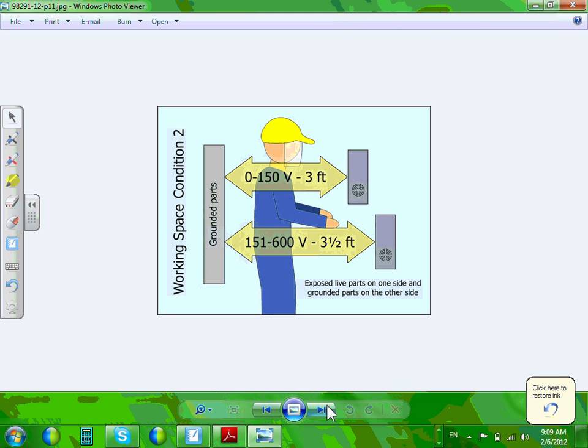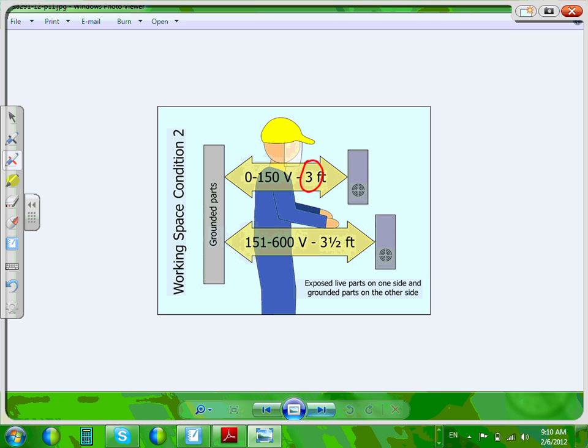If you go to the next one, look at this one. This is a grounded wall. Everybody knows what a non-grounded wall is: sheetrock wall, wood. A grounded wall is block, concrete, metal, or anything. Okay, if you go to this, actually, it continues to be 3 feet. The only thing that changes is if your voltage is 480 or 600, then they add another half a foot. Does that make sense? They add another half a foot. Really, the only thing that changed right now is they add a half, minimum 3. They add half a foot if your system is bigger, a big boy system. Okay? That's condition 2, that grounded wall.